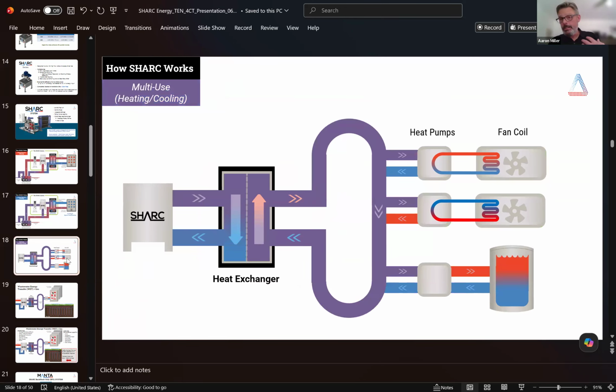And when you're fully leveraging the SHARC's value prop, and this is where we get into the district, is when you're using sanitary to support an ambient loop, right? So now instead of moving hot water around, I'm moving 60 to 80 degree F water around, and I can have heat pumps connected to that same loop doing simultaneous heating, cooling, and hot water production. And the more heat pumps you put on that loop doing different loads and sharing that ambient water, the loop becomes really self-sufficient. And now we're just using the sanitary water, the SHARC, or the geothermal loop, again, think of it that way, to just keep that loop trimmed in that ideal range so that these heat pumps are maximizing the efficiency and capacity. It's really the same gig.